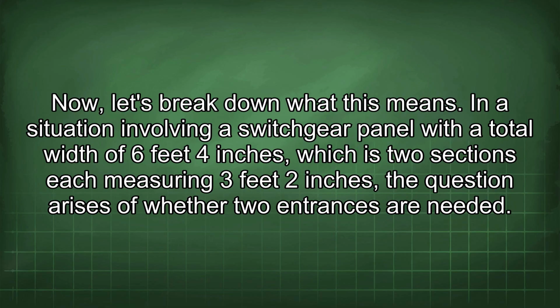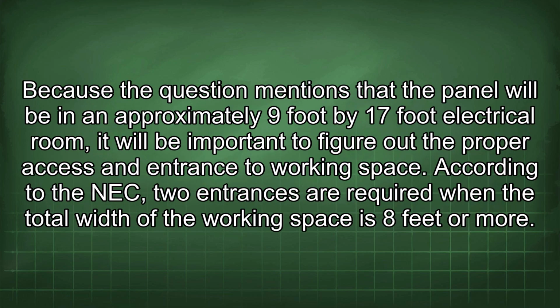In a situation involving a switchgear panel with a total width of 6 feet 4 inches, which is two sections each measuring 3 feet 2 inches, the question arises of whether two entrances are needed. Because the question mentions that the panel will be in an approximately 9 foot by 17 foot electrical room, it will be important to figure out the proper access and entrance to working space.